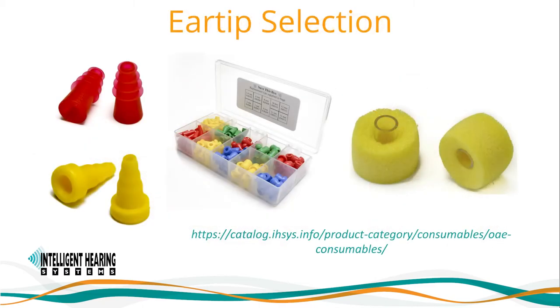There are a variety of ear tips you can choose from. Please visit our online catalog for a selection of available ear tips. Correct ear tip selection is critical for sealing the ear canal and obtaining good quality OAE measurements. Always use the largest size probe tip possible, since a tight seal will ensure a strong signal is sent into the patient's ear and help keep out any environmental noise from contaminating the response. When using the 10D OAE probe on newborns, ensure that when placing the ear tip on the probe, you leave a small cavity approximately 1 mm at the edge of the cover tip for the collection of vernix or fluid debris that may still be present in the ear canal after birth. This will ensure that the probe cover tip does not get occluded.